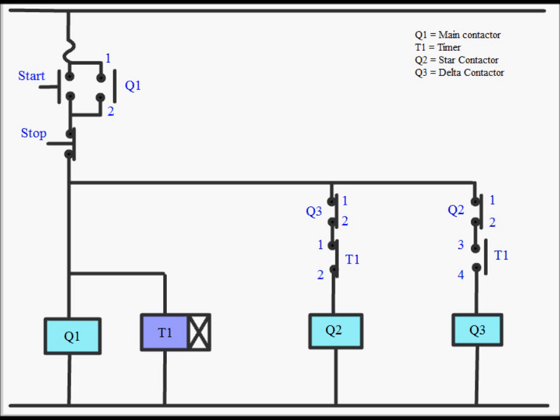So this is a control circuit for the star delta starter. When the start button is pressed, contactor Q1, timer T1 and Q2 all three are operated. In this mode when Q1 and Q2 are operated, motor is running in star mode.